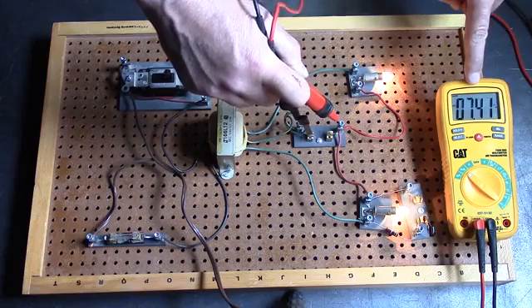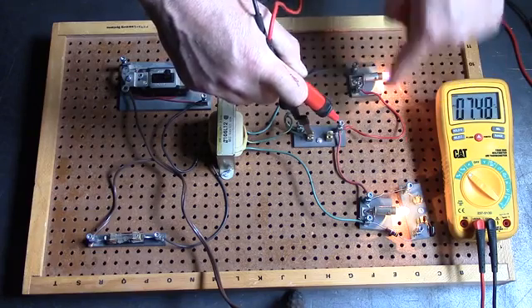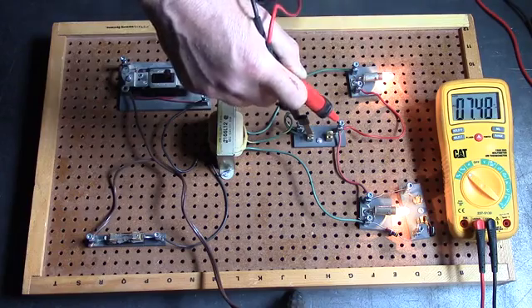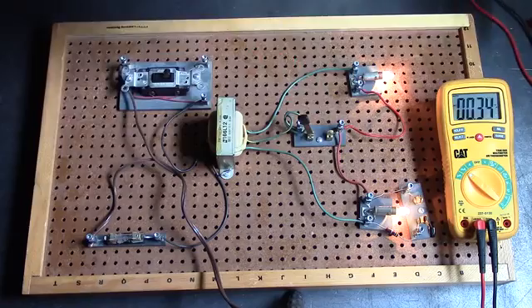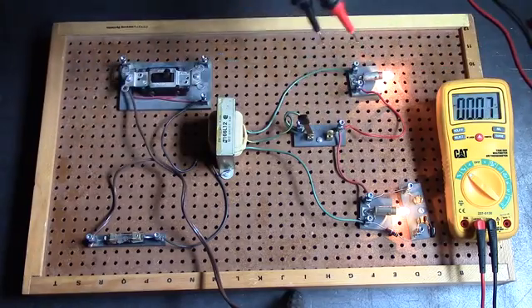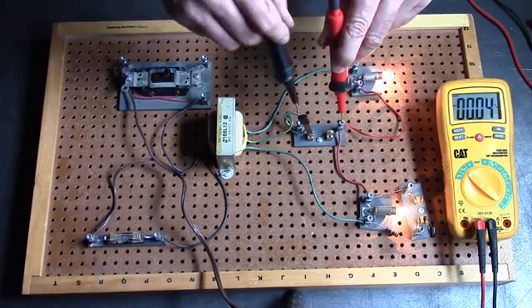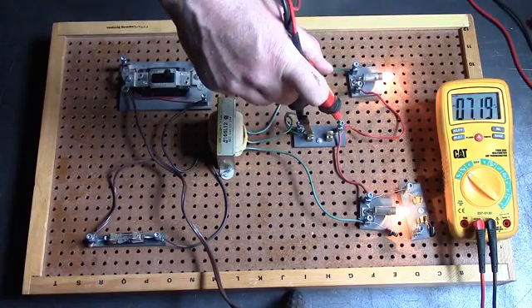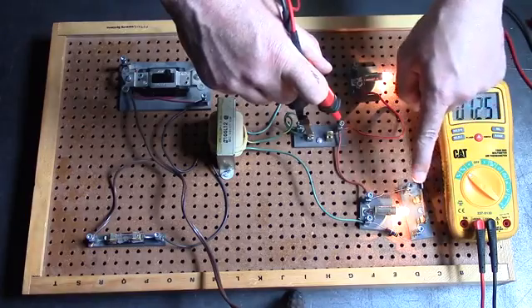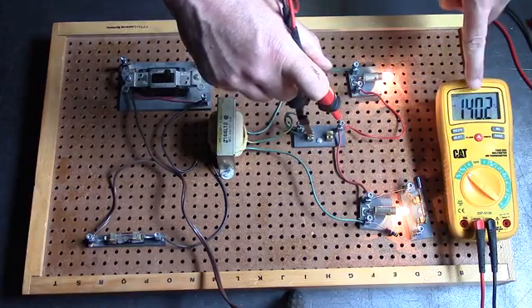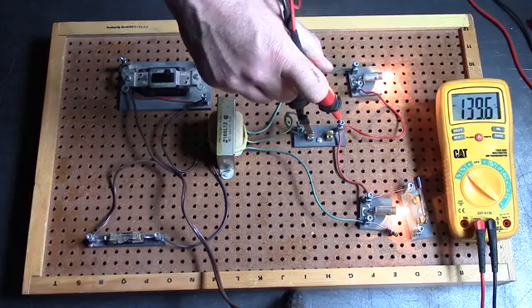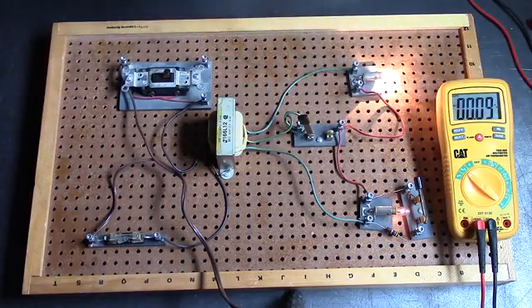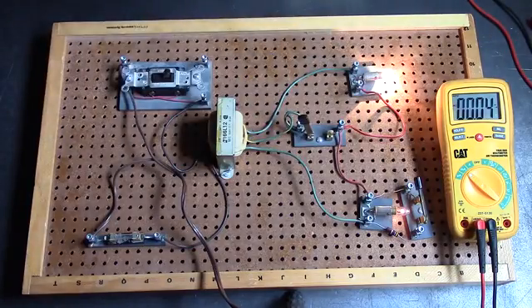If I would take this resistor out of the picture and balance up the two lamps again I've only got about seven milliamps because the lamps are almost identical. There's a very small amount of current flowing on the neutral and of course if I take the neutral away the circuit still functions. That seven milliamps is not reflecting enough of a problem that the lamps are affected in any way. But of course I've got an imbalance where I'm relying on the neutral path to carry that 140 milliamps. If I take it away and I take that path out of the circuit of course then I get my imbalance in voltage drops.